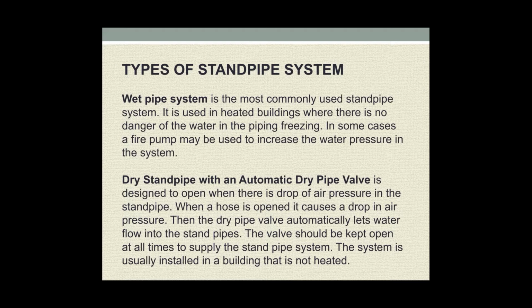Types of standpipe system. Wet pipe system is the most commonly used standpipe system. It is used in heated buildings where there is no danger of the water in the piping freezing. In some cases, a fire pump may be used to increase the water pressure in the system.